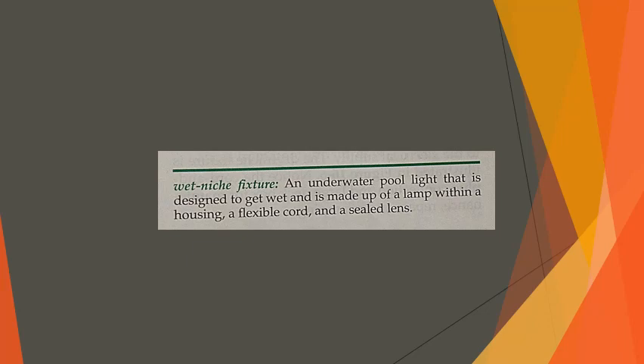Only UL or other lab tested and listed lighting fixtures are to be installed. Fixtures may not exceed 150 volts between their conductors. Fixtures that operate above 15 volts must be GFCI protected. When installed, the fixture's top edge must be at least 18 inches below the normal water level. Note that certain fixtures may be installed at a minimum of 4 inches below the normal water level, only if identified for that use. If the fixture is installed at that depth, it shall have some inherent means to protect it against overheating.